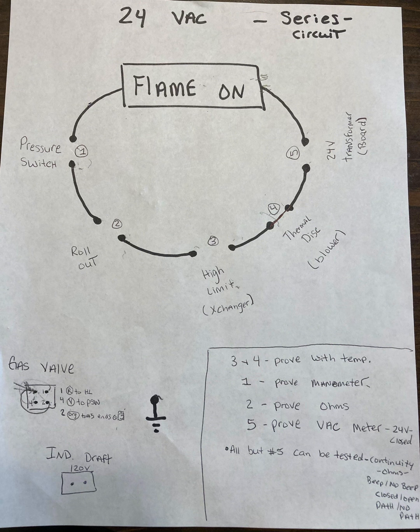The control circuit, while I'm thinking about it, is a beautiful example of a series circuit versus something like a parallel circuit, how we see most of our motors being run. Series circuits are fairly easy to navigate, especially using the hopscotch method. Let's go back to that pressure switch. Every pressure switch in every furnace is going to be a little bit different, and the great news is what it's rated for is right on the pressure switch. When those pressures are met, that switch closes.